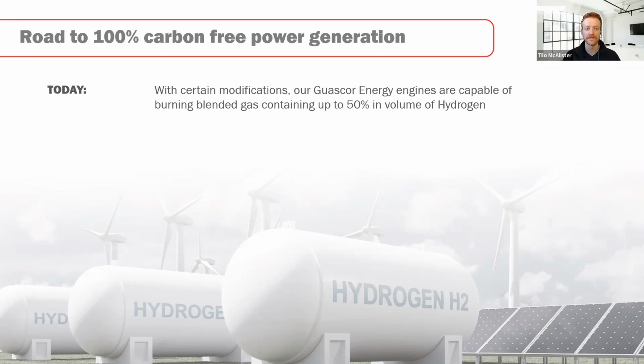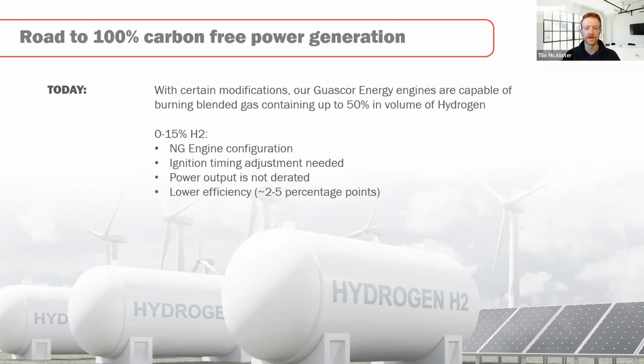What we learned from Guascor is that with certain modifications, these existing rich-burn natural gas engines are capable of burning a blend of natural gas with up to 50% volume of hydrogen with very little change. Up to 15% hydrogen, we can use the existing natural gas engine configuration, just adjust the ignition timing, and we don't need to derate the power output. So if this generator puts out a megawatt on natural gas, it can put out a megawatt on natural gas with 15% hydrogen, but at slightly lower overall efficiency—maybe it was 37% efficient on natural gas, and it might go down to 34 or 35% when we blend in some hydrogen.